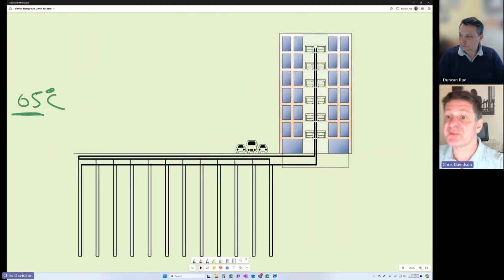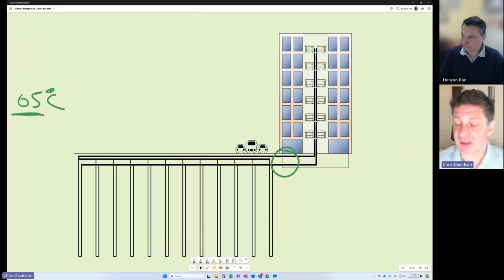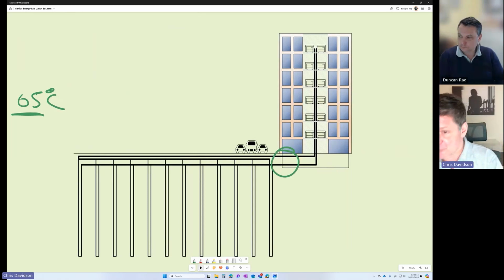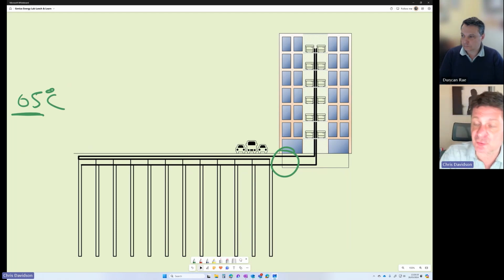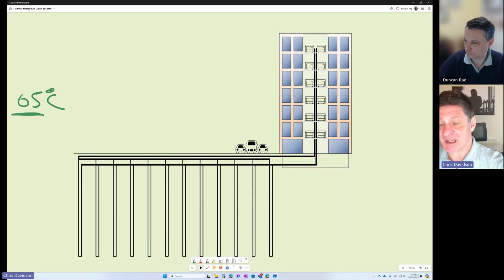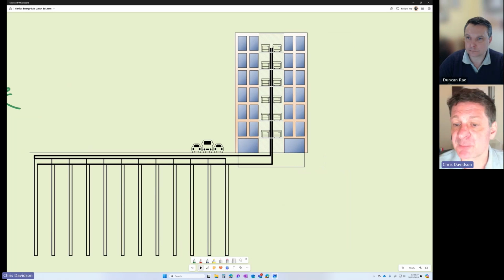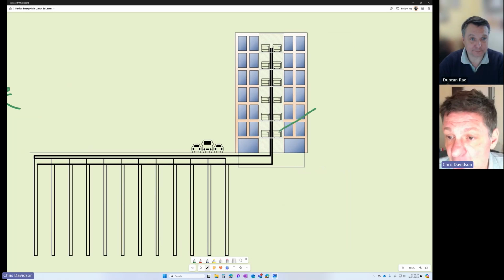Now let's look at a distributed plant model. So right away we can see we've got no plant here in the basement. We don't even have any pumps. And that's one thing we've pioneered in the marketplace, is getting rid of those central pumping arrangements that were previously thought to be required. We've now got heat pumps in each individual dwelling, and those heat pumps can be delivering heating, domestic hot water at that 65 degrees.